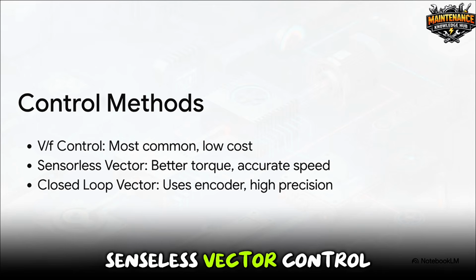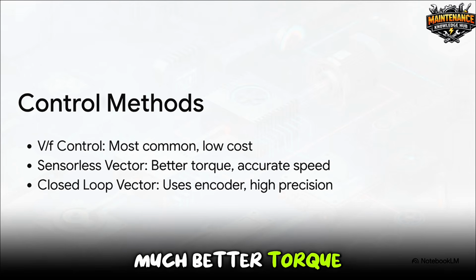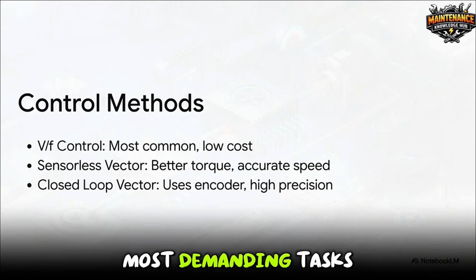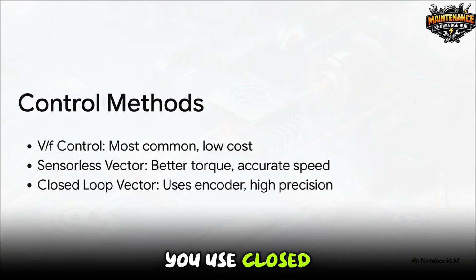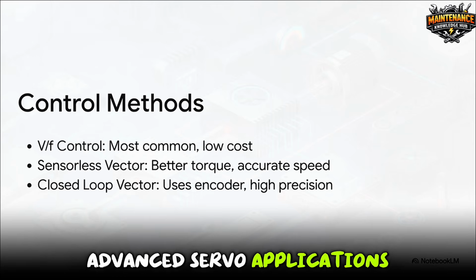Next up is sensorless vector control, which gives you much better torque control and more accurate speed regulation. And for your most demanding tasks, you use closed-loop vector control. This actually uses encoder feedback directly from the motor for incredibly high precision, typically used in advanced servo applications.